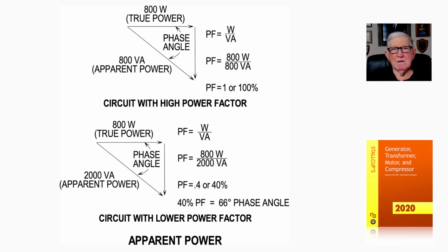That's good. Now, all the calculations in the National Electrical Code in accordance with 220.12(A), informational note. I'll say that again, you can look it up, 220.12(A), informational note. Everything's taken at 100% power factor, so all your calculations come out based upon 100%, that you see right there. Sometimes people say, well, James, you didn't figure this, you didn't figure that, you didn't figure power factor. No, you're not supposed to figure that situation without the problems there.